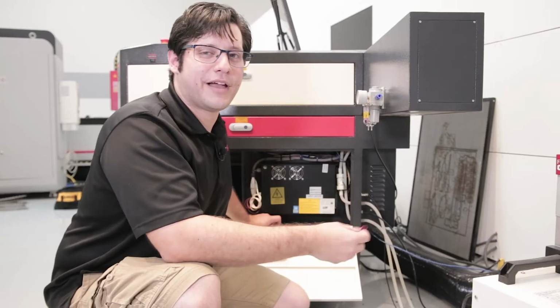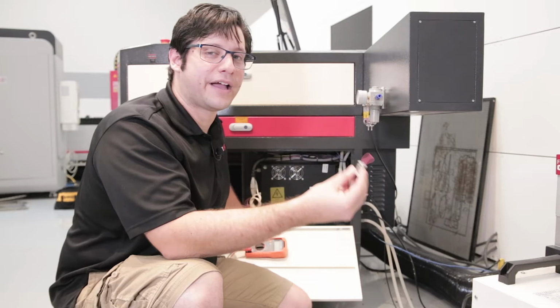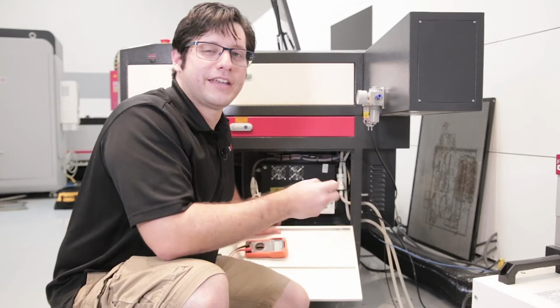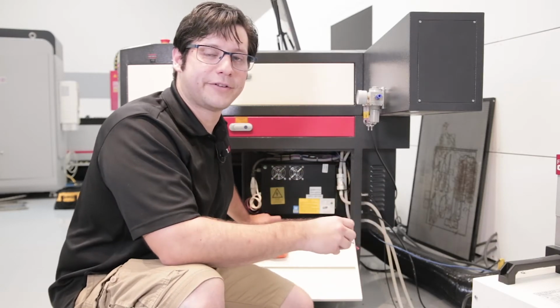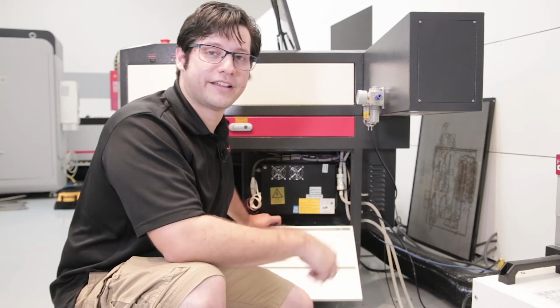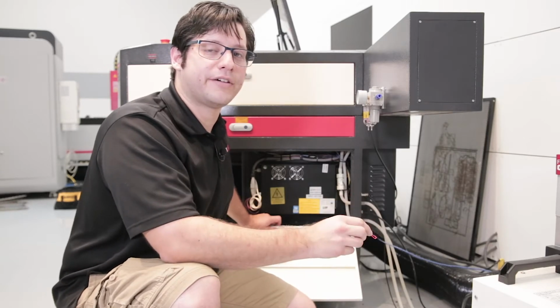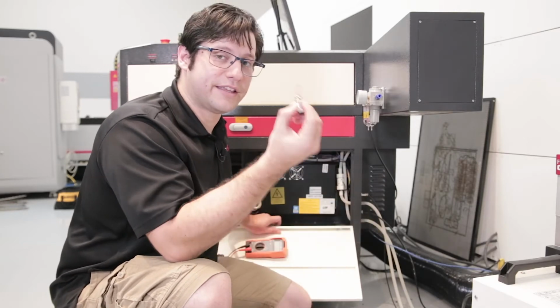At this point, if you do have continuity, go ahead and plug in your bypass for your chiller and see if it fires from your control panel. If it does fire, that's great. Go ahead and contact tech support. If it doesn't fire, we're going to have to leave this in its place. Then we're going to move on to checking the continuity on the power supply.